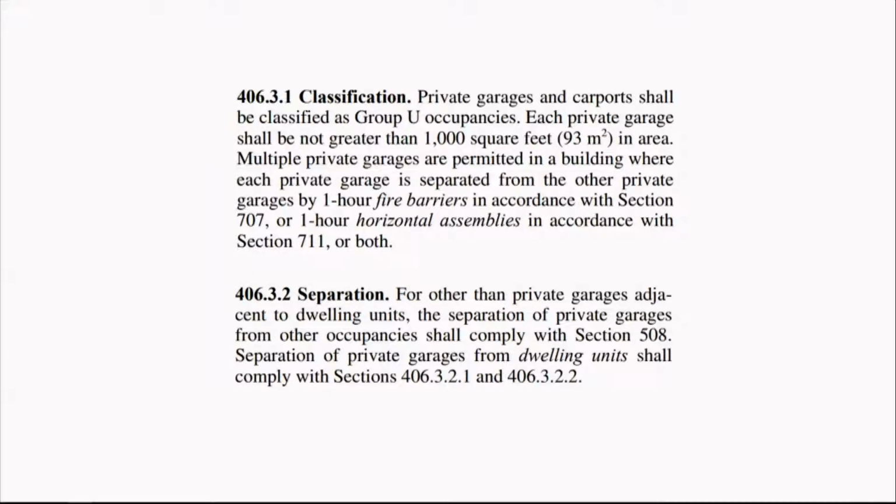For other than private garages adjacent to dwelling units, which ours are not in this case, because the dwelling units are in a separate building on the other side of a fire wall, the separation of private garages from other occupancies shall comply with section 508.